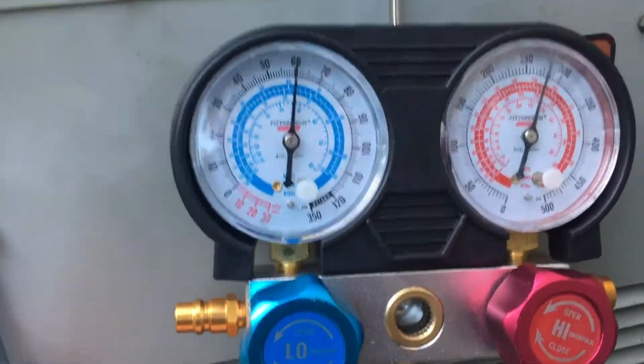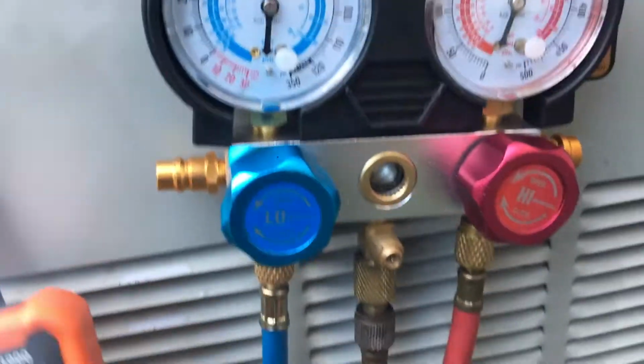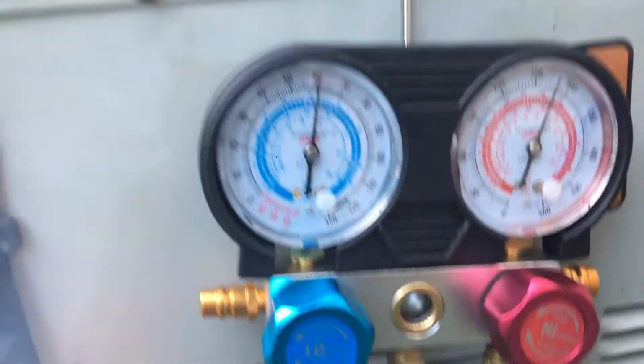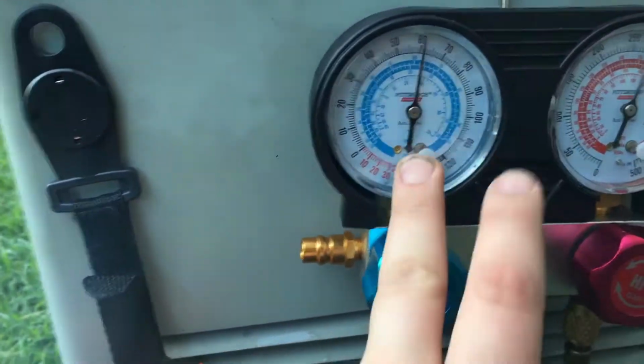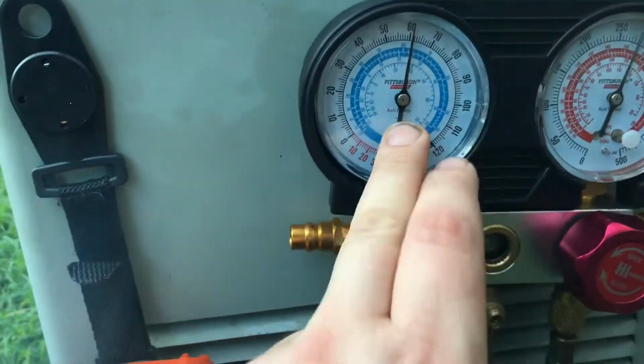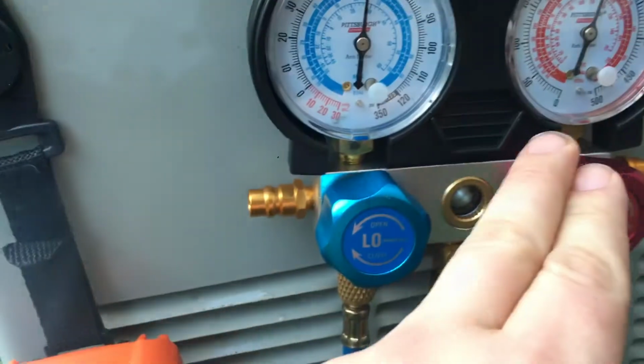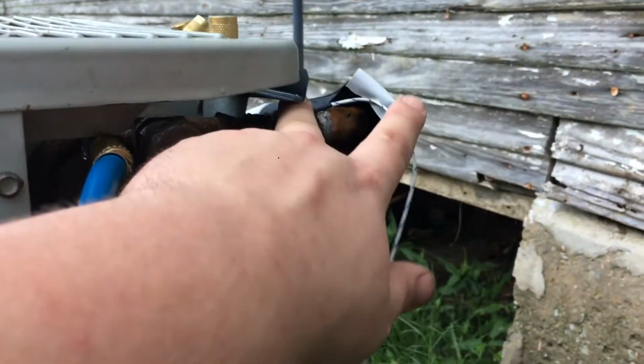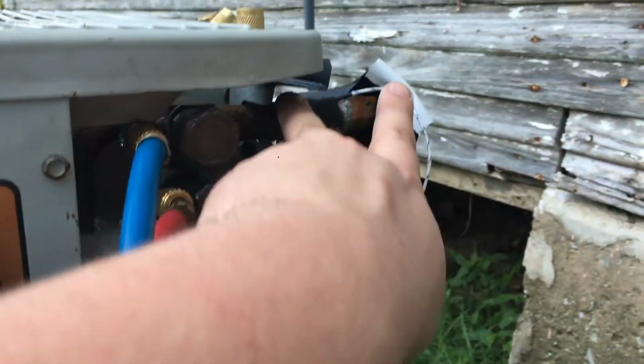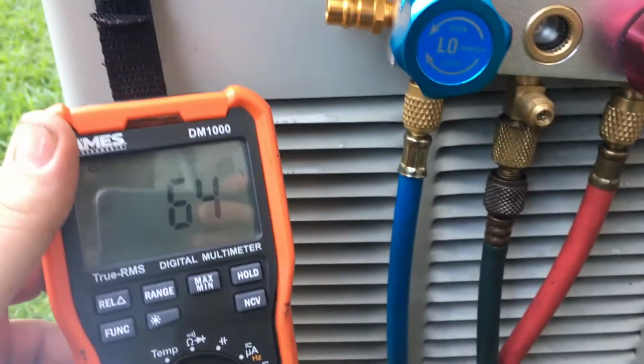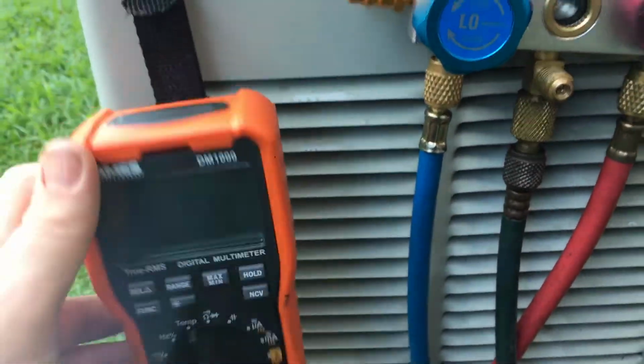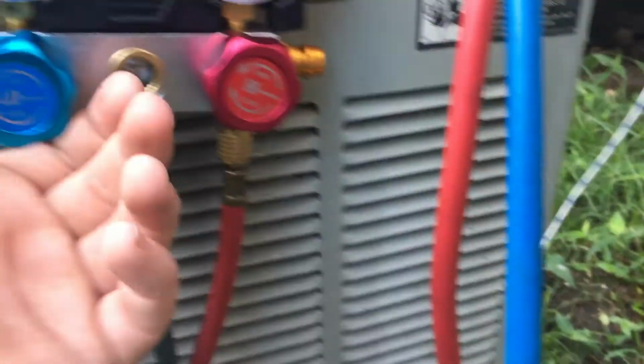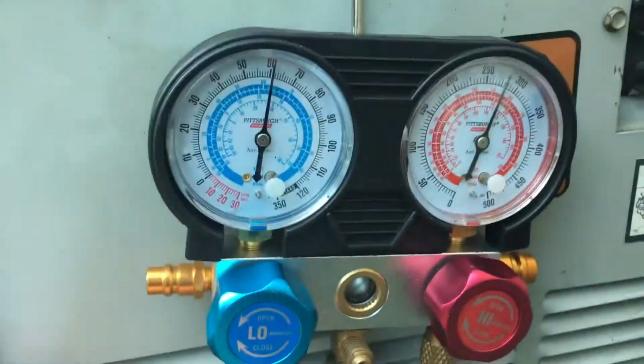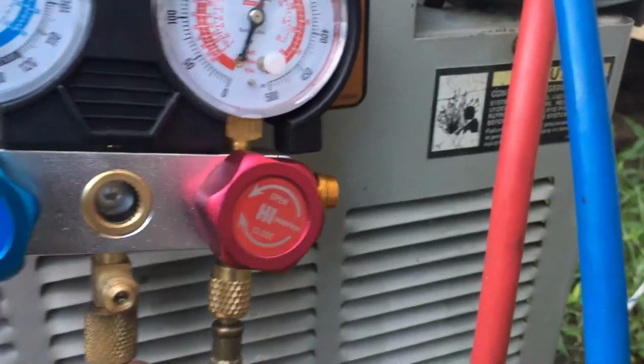Alright, I believe that's just about got it now. We're sitting at about 23 degrees of superheat, and yes, this time I'm checking the low side, not the high side. And I do have my thermocouple on the suction line. Suction line is beer can cold, and it's sweating. Now we're up to 64 on that. So, I believe it's charged. Well, the app actually says it's charged.